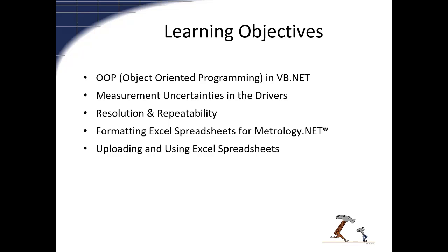We're going to talk about how the drivers are doing their measurement uncertainties. And you can see in the code how they come in and do their calculations. We're looking at the resolution and repeatability, how the drivers will add that back into the measurement uncertainty budget.